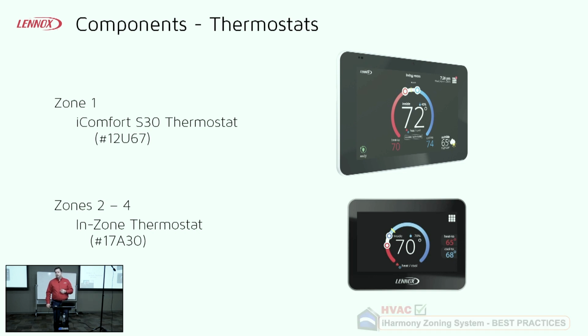So, like I mentioned, S30 is going to be zone 1 always. So you want to be cognizant of where you install that in the home. That's going to be your main control center. The zones 2 to 4 will use the 17A30 in-zone sensor. What's important to know about that is you can adjust temperature there for that specific zone. You can see alerts and things like that, but you can't really change modes or change schedules from that in-zone stat. So a lot of times that can cause some confusion because sometimes folks think that those in-zone stats are like an S30, where you can just control everything from every single component. But the S30 is going to run the show. That's going to be your main control panel and also provide your zone 1 temperature.